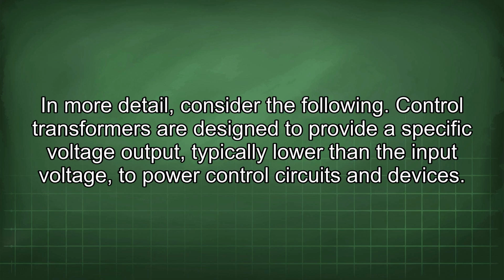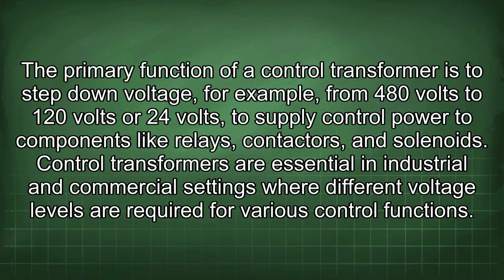Control transformers are designed to provide a specific voltage output, typically lower than the input voltage, to power control circuits and devices. The primary function of a control transformer is to step down voltage, for example, from 480 volts to 120 volts or 24 volts to supply control power to components like relays, contactors, and solenoids. Control transformers are essential in industrial and commercial settings where different voltage levels are required for various control functions.